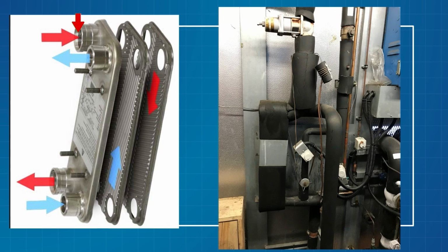Before any work is done to it, well, that means on the primary side, this is the warmest part of my evaporator. So I bring in the two warmest together, right? And then I have the coldest, where it comes out is the coldest spot on the primary side. So technically it's counterflow, but really what I'm doing is making the warmest match the warmest, and the coldest match the coldest.